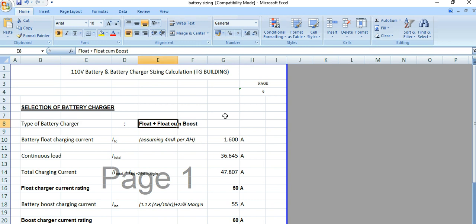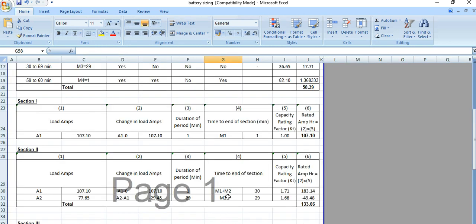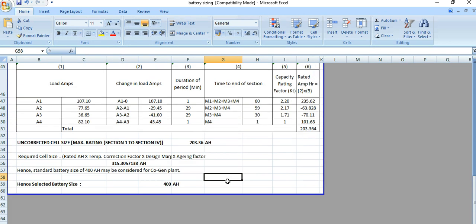The battery float charging current is 1.6 ampere, because we have assumed 4 milliampere per ampere hour. The battery was sized, if you can recall, at 400 ampere hour.